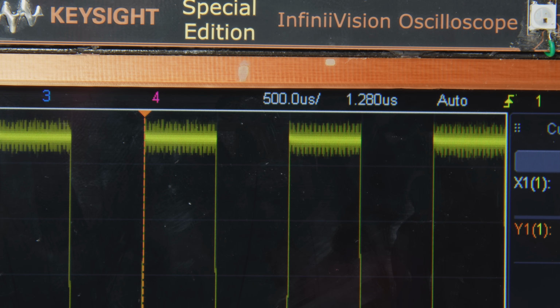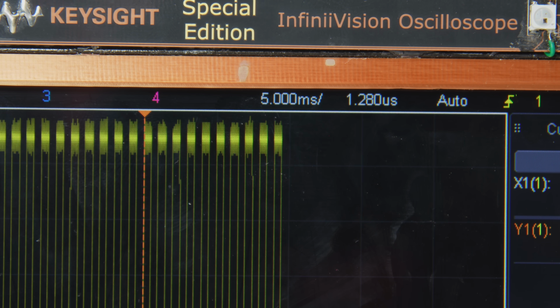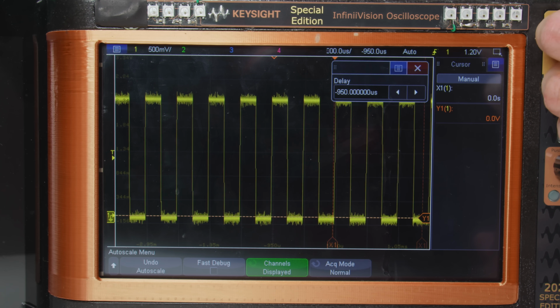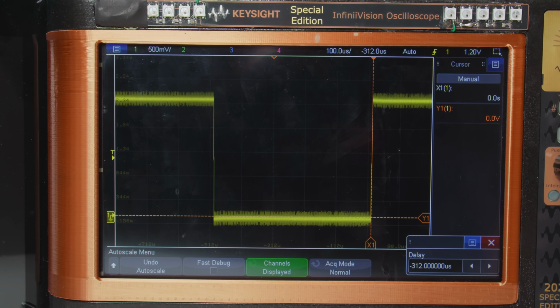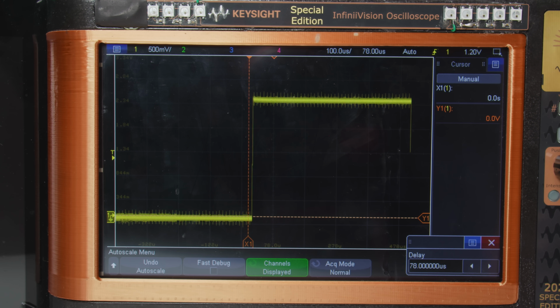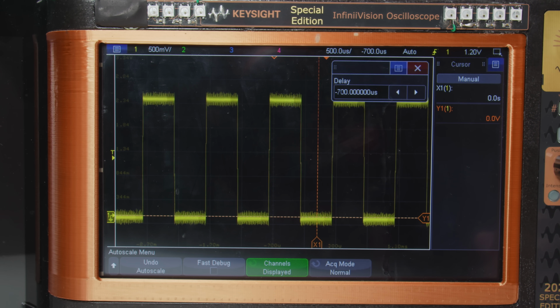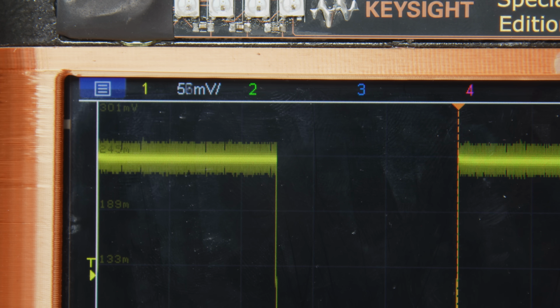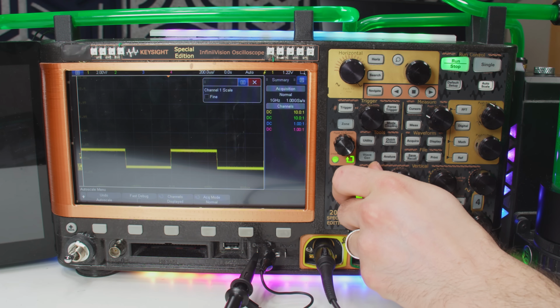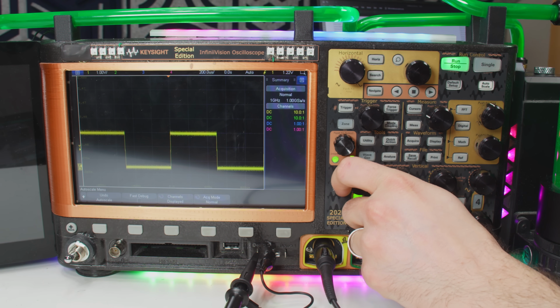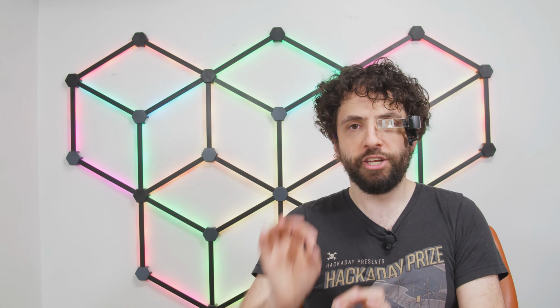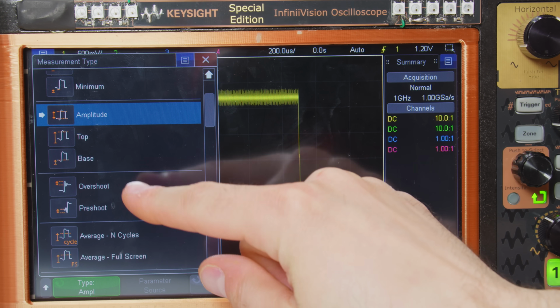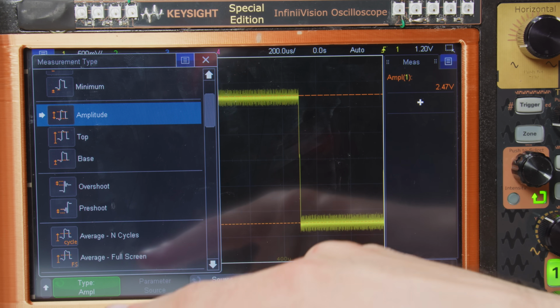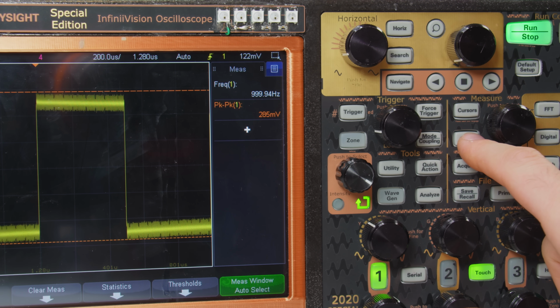The primary setting for the X dimension is time per division, in other words, how much time each grid square represents. You want to adjust this so whatever you're looking for fills the screen. You might want to see the whole curve, zoom in on a particular part, or back out to watch the greater pattern. The setting for the Y dimension is volts per division. Adjust this so your signal fills the screen. Don't rely on the grid lines for measurement, they're really just for reference. If you need exact numbers, switch on an analysis or invoke the cursor. These generally both have specific buttons on the front panel to bring them up.